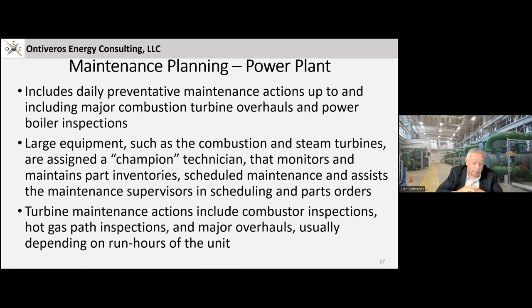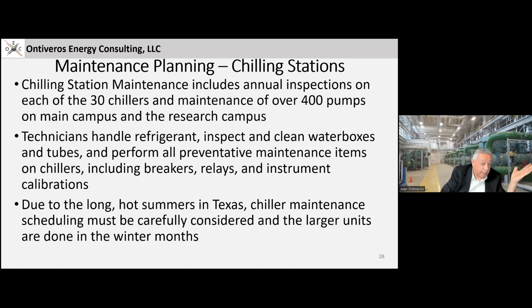Turbine maintenance actions, for example, involve combustor inspections, hot gas path inspections, major overhauls. Usually it depends on run hours. That's how we did it. Number of hours of the unit is when we would schedule these kind of things. Chiller station maintenance involves annual inspections on all the chillers. Our standard was we opened up every chiller every year. So it was a very big challenge, 30 chillers. And I think it's more than 400 pumps. I said put 400 pumps in the presentation here, but I hear that number is probably larger. Plus, we also have a remote research campus that we did.